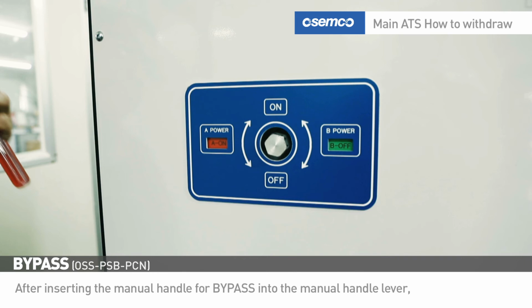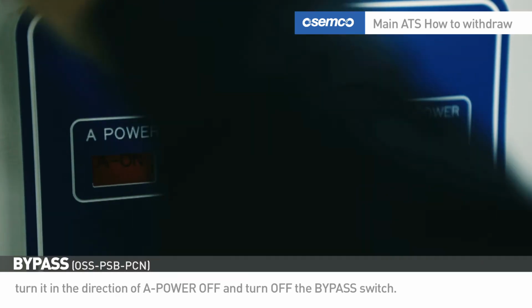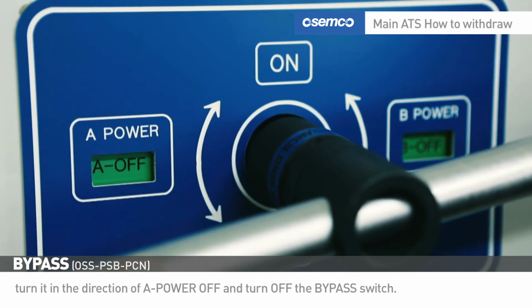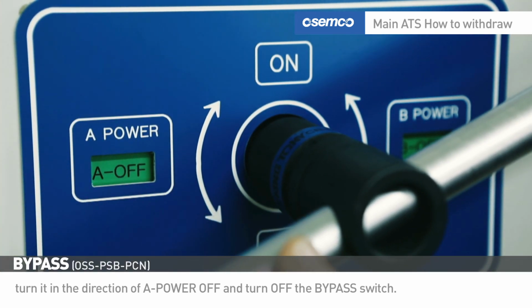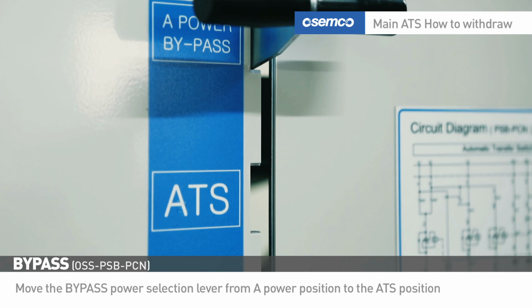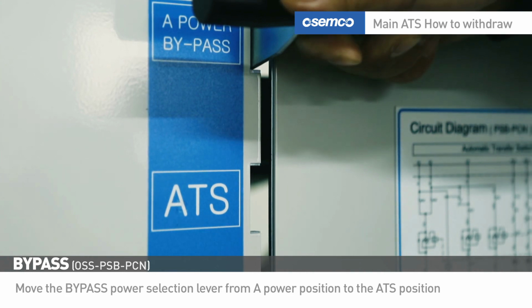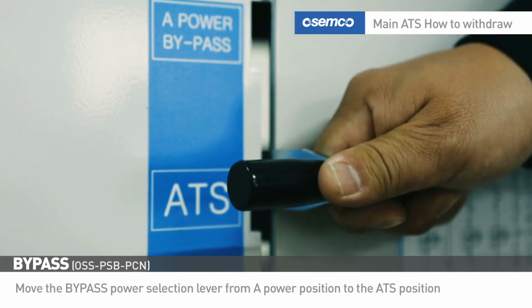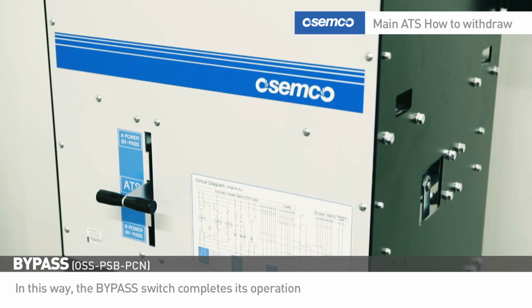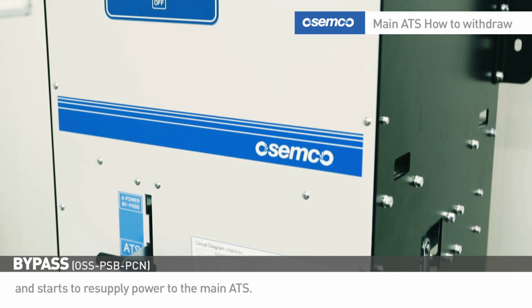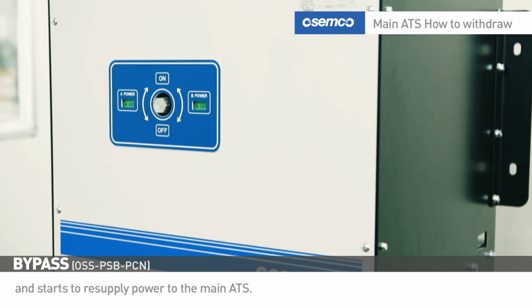After inserting the manual handle for bypass into the manual handle lever, turn it in the direction of A power off and turn off the bypass switch. Move the bypass power selection lever from A power position to the ATS position. In this way, the bypass switch completes its operation and starts to resupply power to the main ATS.